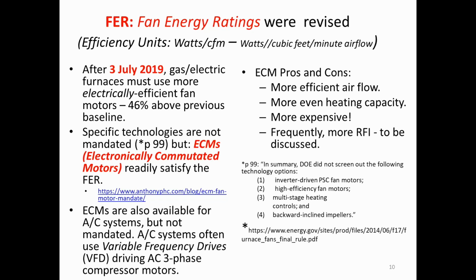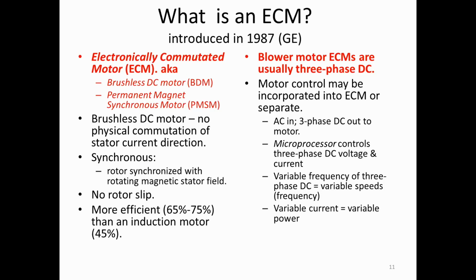And I say it is a mandated problem because it's very difficult to buy a new furnace which does not have an ECM motor. HVAC people sometimes call this law the ECM mandate, which is not really true, but in practice, that's what it's turned out to be. Almost everybody manufacturing furnaces is now using an ECM from one manufacturer or another to drive the blower motor. So what is an ECM?